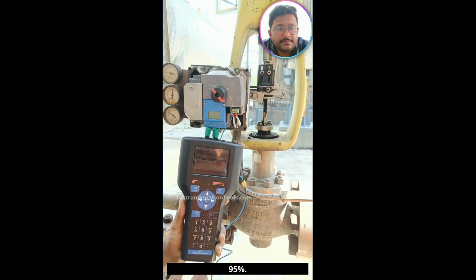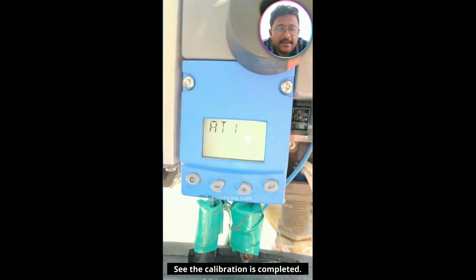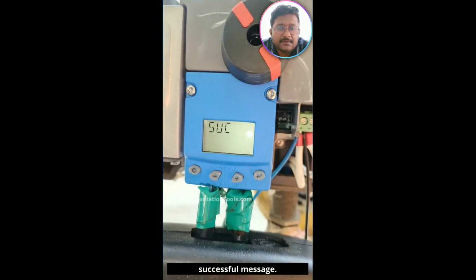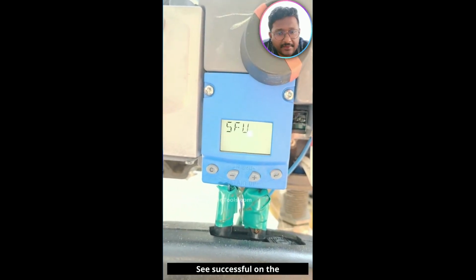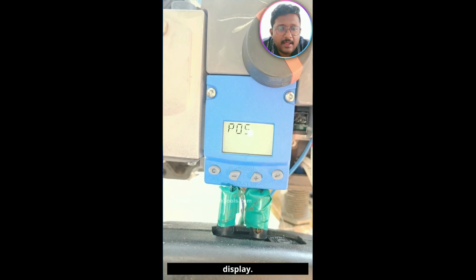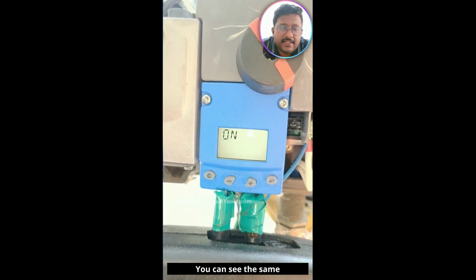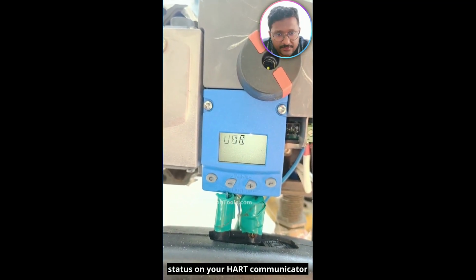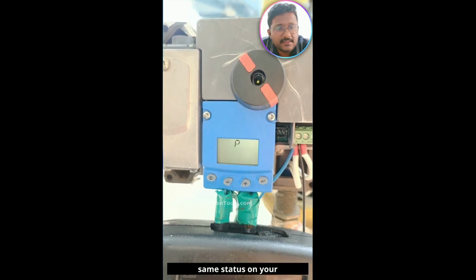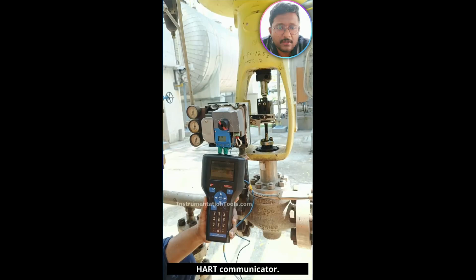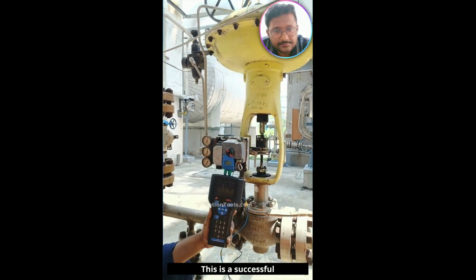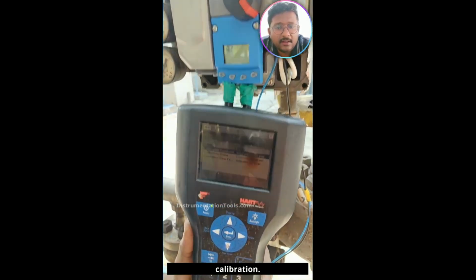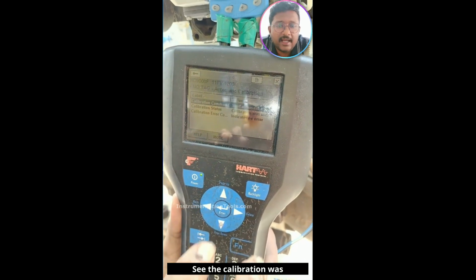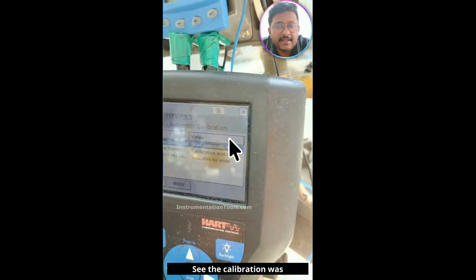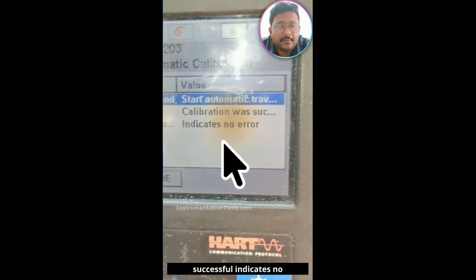95 percentage. See, the calibration is completed. You can find the successful message. See, successful on the display. Calibration is completed. You can see the same status on your HART communicator also. Now we will see the same status on your HART communicator. This is a successful calibration. See, the calibration was successful, indicates no error.